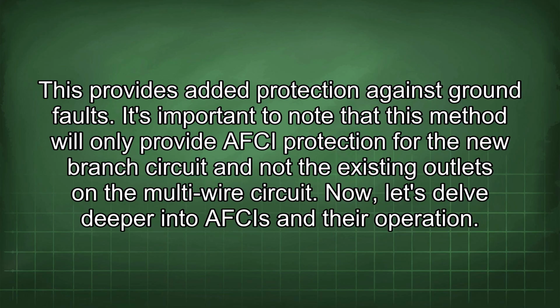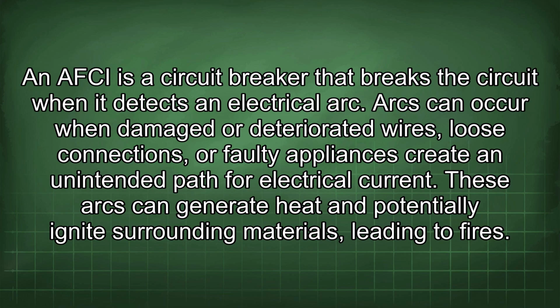It's important to note that this method will only provide AFCI protection for the new branch circuit and not the existing outlets on the multi-wire circuit. Now, let's delve deeper into AFCIs and their operation. An AFCI is a circuit breaker that breaks the circuit when it detects an electrical arc. Arcs can occur when damaged or deteriorated wires, loose connections, or faulty appliances create an unintended path for electrical current. These arcs can generate heat and potentially ignite surrounding materials, leading to fires.